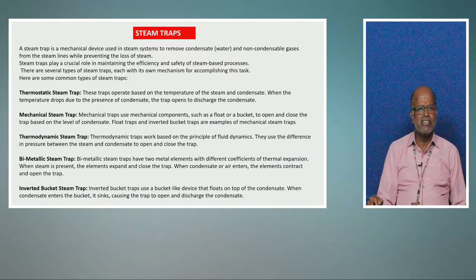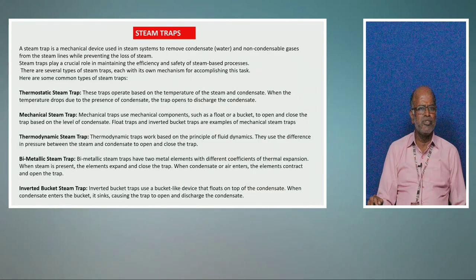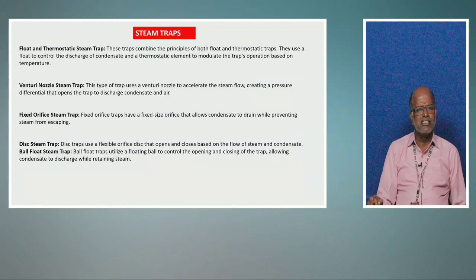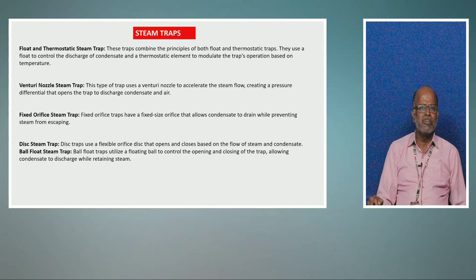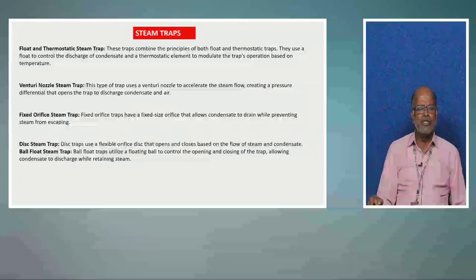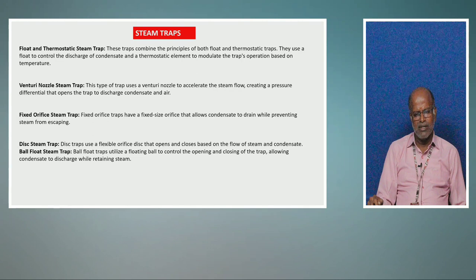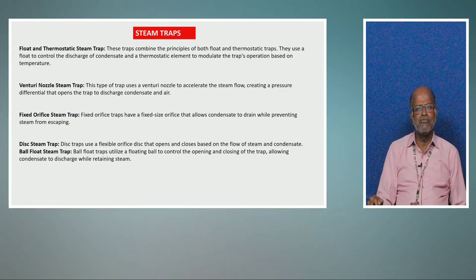Next is the steam trap. A steam trap is a mechanical device used in steam systems to remove condensate and non-condensable gases. There are various types: thermostatic steam trap, mechanical steam trap, thermodynamic steam trap, bimetallic steam trap, inverted bucket steam trap, venturi, fixed orifice, disc trap, and ball float steam trap. Steam traps are mostly used to remove condensate from pipelines wherever steam is used, such as for sterilization in the fermentation industry. As the pipeline travels a distance, condensation of steam can occur and must be removed at regular intervals — if not, it leads to water hammering of the pipeline, which is dangerous.